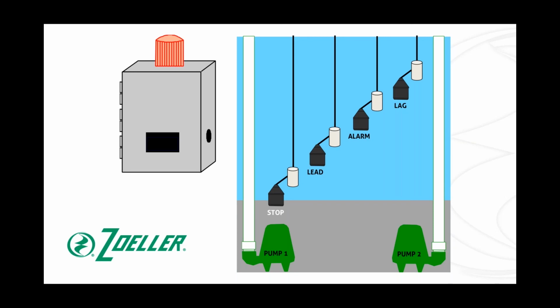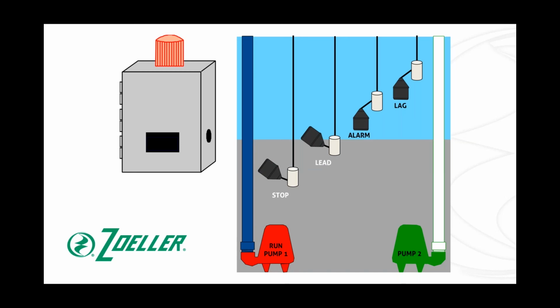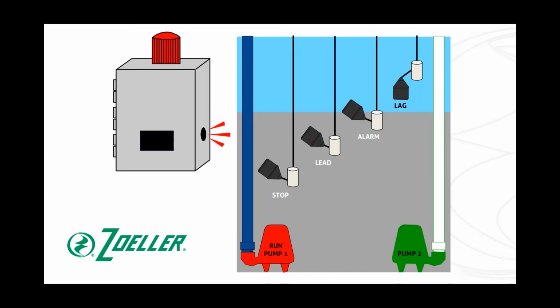So now let's get into the real differences here. This time water comes in, and let's just say again that water's coming in at a much higher flow rate than normal. So as it's coming in, the stop float comes up, the lead float rises, and when it does, it calls for pump 1, or our lead pump this time, to come on. It begins pumping. Again, we've said that the water is coming in so fast this time that pump 1 was not able to keep up with the flow rate. So the water level has risen to such a point now that it has activated, in my setup here, the alarm float. And I have chosen to do it this way, and I want to explain.